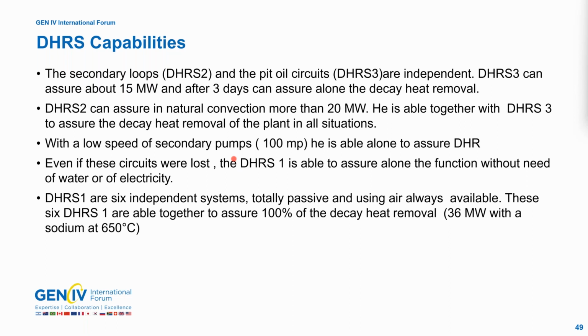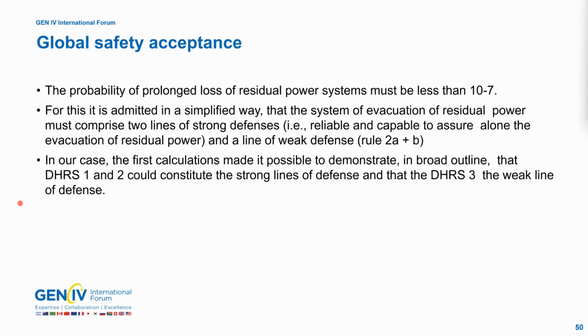And even if all the circuits are lost, the DHRS1 is able to assure the function alone, without need of water and without need of electricity. The DHRS1 are 6 independent systems, totally passive, using air that is always available. They are able together to assure 100% of the decay heat removal. In fact, the calculations were made with 5 independent systems and 1 that was out of order.